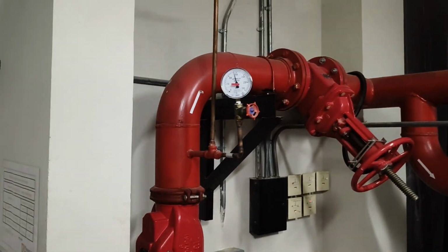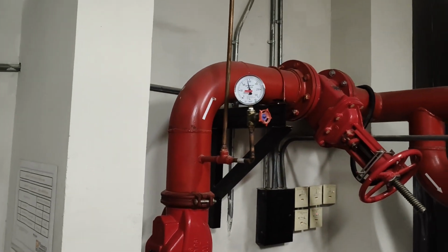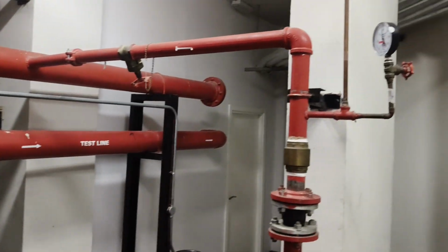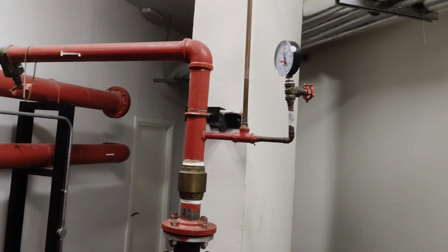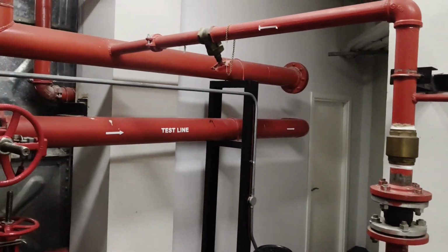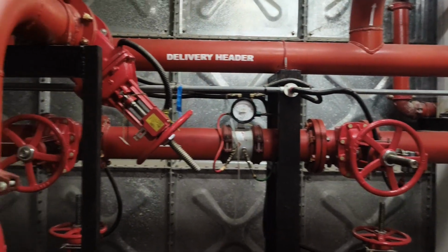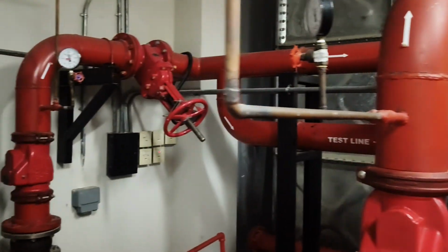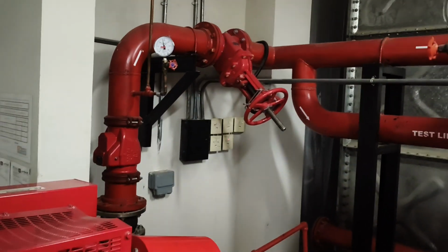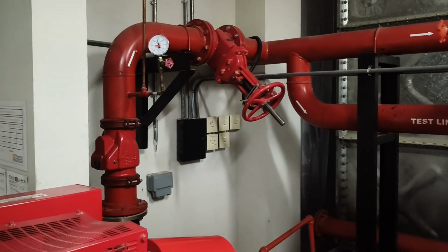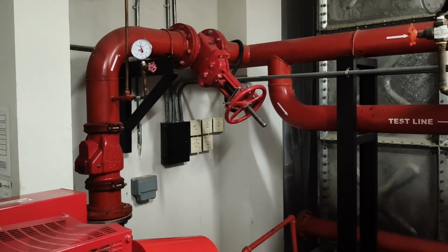Also, the sensing line of the diesel is connected, and that of the jockey pump is also here with its own pressure gauge individually. So this pump room has been made so that even if you close a valve somewhere, you can individually get the different pressures.